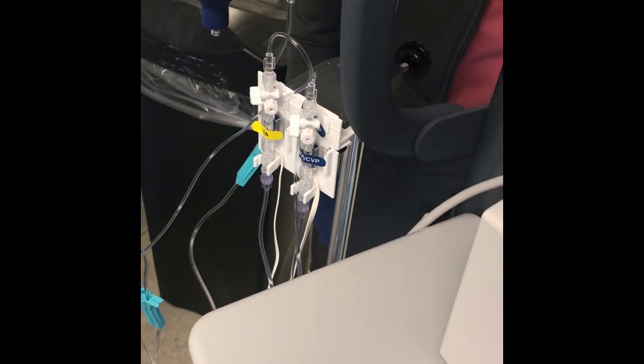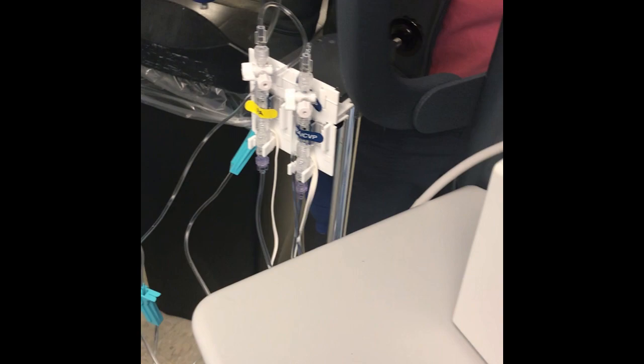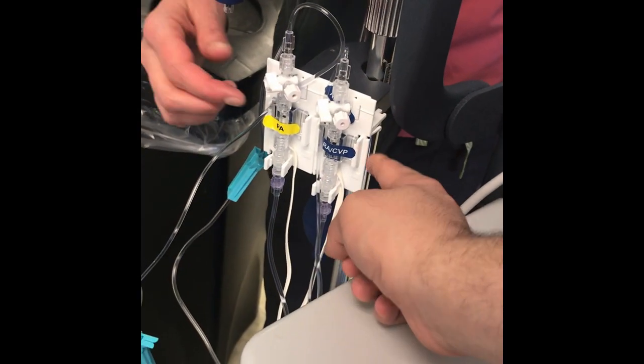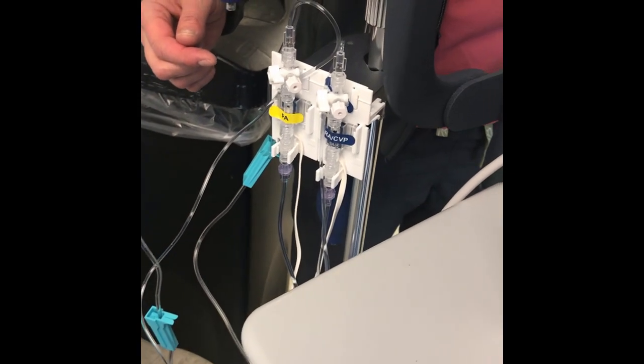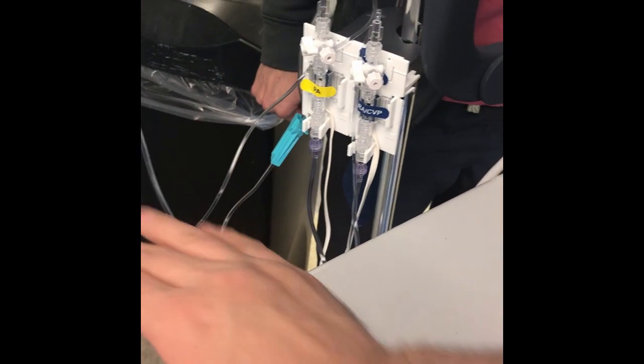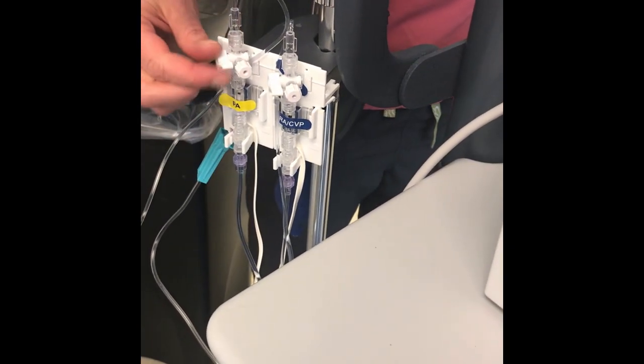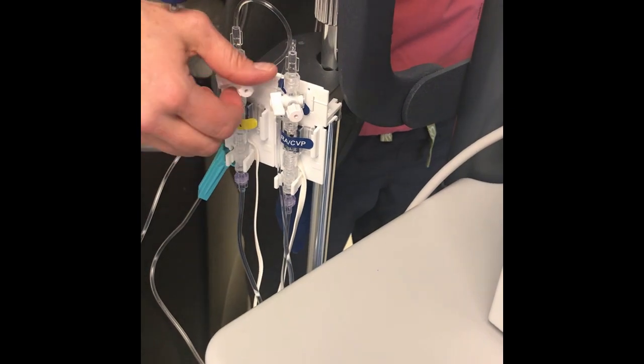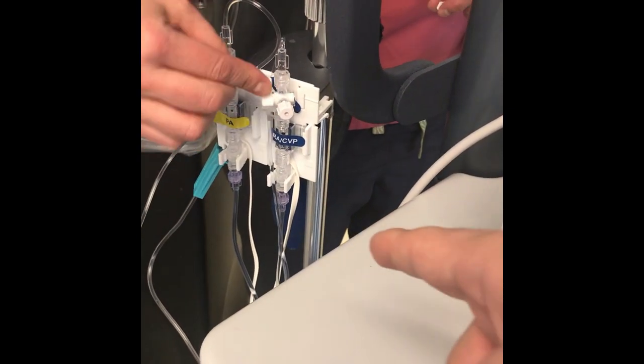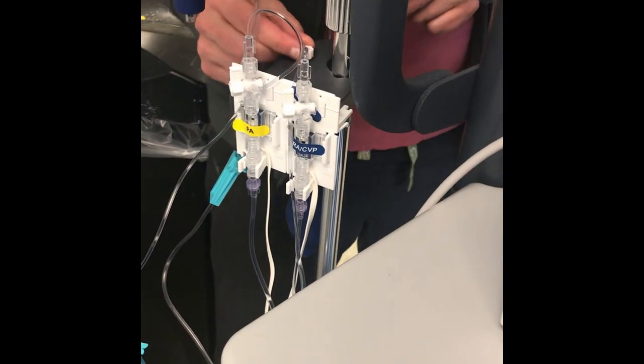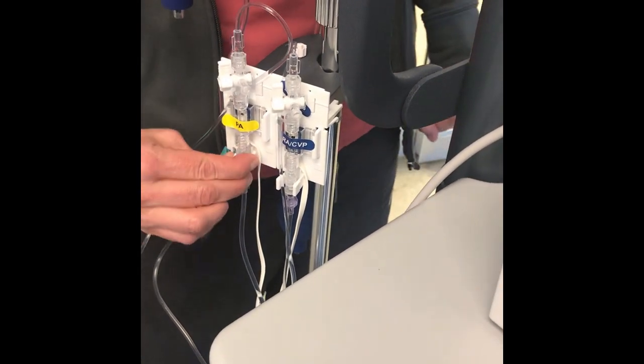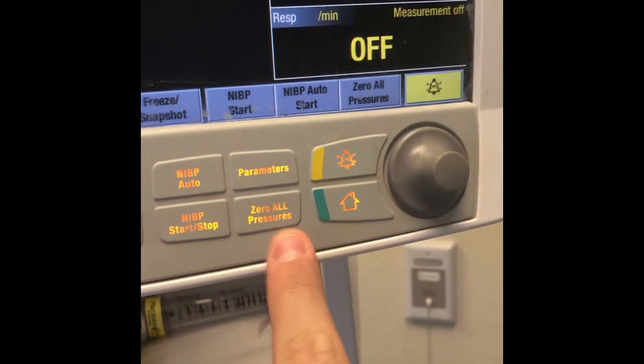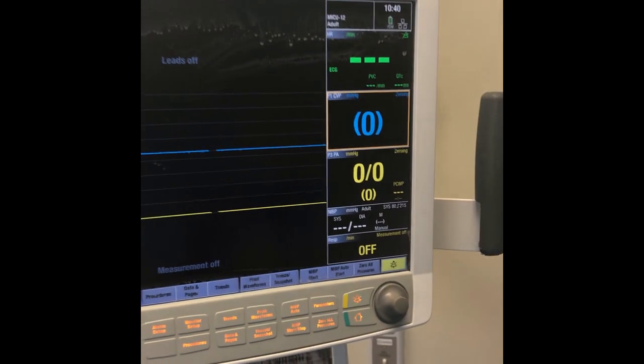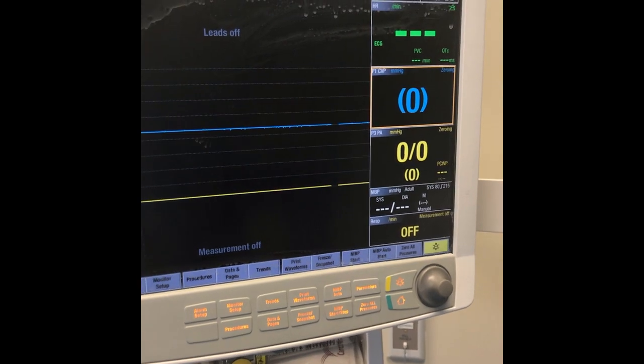After your connections are ready, you should make sure that the lines are accurately zeroed. And what we do, you pull up the sensors to the level of the heart of the patient. So the heart has to be at the same level. And this is how we zero. So first of all, you want to close it, and then you open the cap, and then you do the same for the other one, and then you have to flush it by pressing here. That will give some fluids out, and then you go to your monitor and you press this button that says zero all pressures, and now both the PA and the CVP will be zeroed.